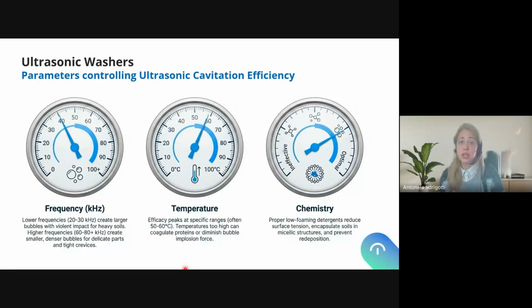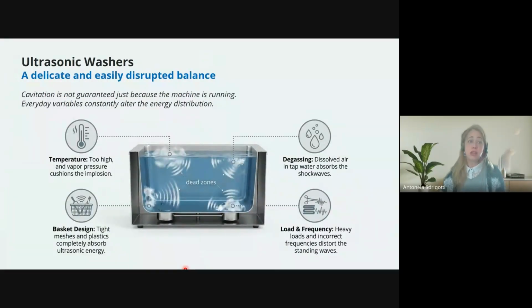So we have to make sure that our enzymes in the detergent will stand the cavitation delivered to the system to clean our instruments, and we will not inactivate these enzymes just because we are making an ultrasonic process, okay? So we have to make sure that we use also the right dose of detergent. More detergent is not always more effective or increasing the effectiveness of a washing process. We have to follow the manufacturer's instructions. Okay, so as you can see, ultrasonic washers have a delicate and easily disrupted balance.